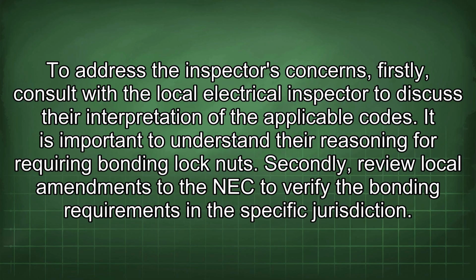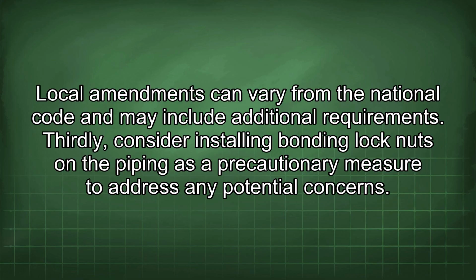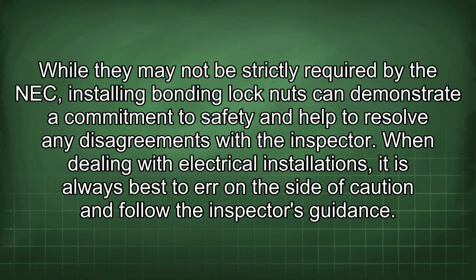To address the inspector's concerns, firstly, consult with a local electrical inspector to discuss their interpretation of the applicable codes. It is important to understand their reasoning for requiring bonding lock nuts. Secondly, review local amendments to the NEC to verify the bonding requirements in the specific jurisdiction. Local amendments can vary from the national code and may include additional requirements. Thirdly, consider installing bonding lock nuts on the piping as a precautionary measure to address any potential concerns. While they may not be strictly required by the NEC, installing bonding lock nuts can demonstrate a commitment to safety and help to resolve any disagreements with the inspector.